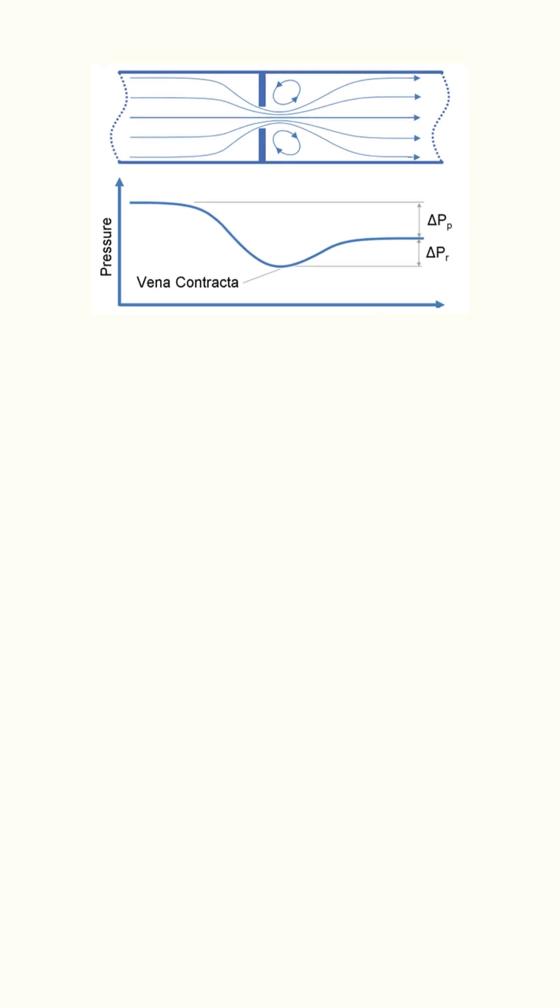When the fluid passes through the valve vena contracta, the flow area decreases, which increases the fluid velocity as per the continuity law. On the other hand, the pressure decreases as per Bernoulli's equation. As the area increases again to equal the outlet pipe area, the fluid velocity decreases and the pressure increases again, but to a pressure less than the original pressure at the control valve inlet.